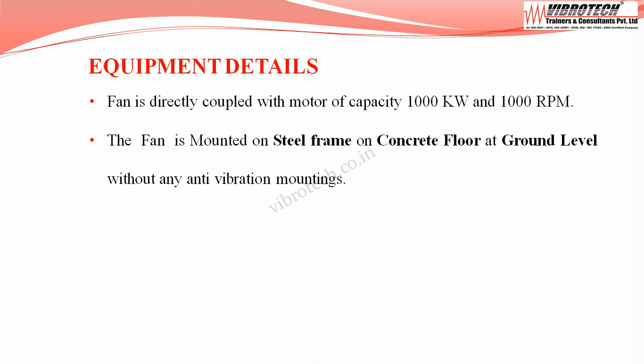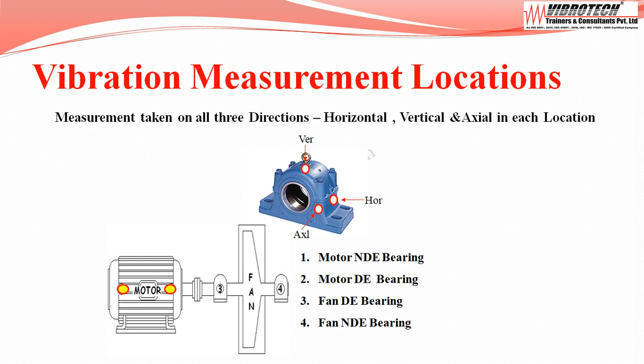Vibration measurements are taken in all three directions: horizontal, vertical, axial, at each location. Measurement locations are motor non-drive end bearing, motor drive end bearing, fan drive end bearing, fan non-drive end bearing. Vibration data are collected in terms of displacement in microns peak to peak and velocity in millimeters per second RMS.